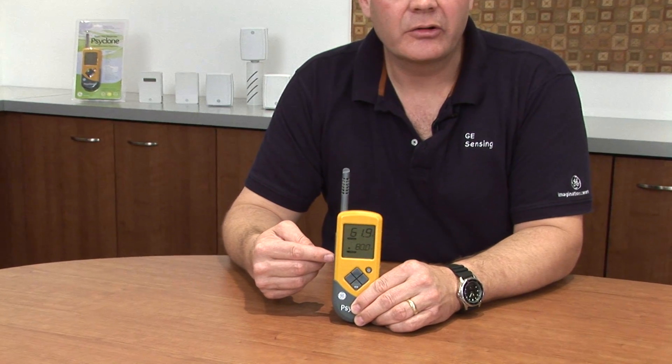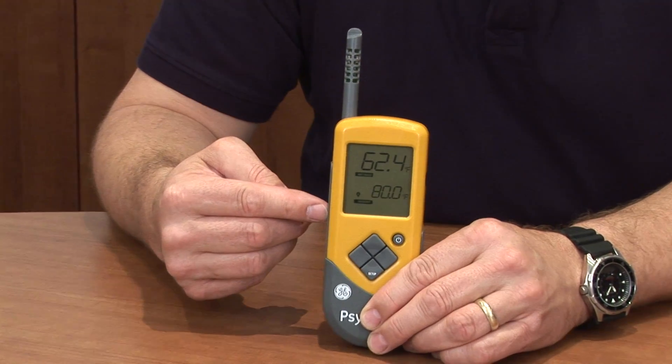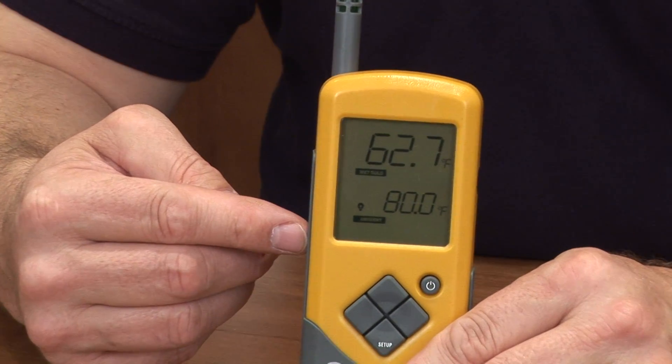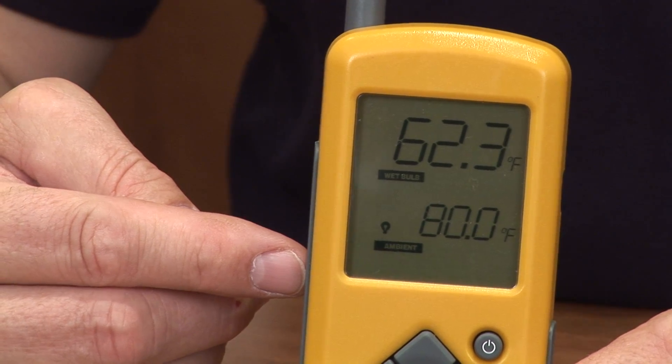The unit itself is robustly constructed with a rubberized hand grip and a belt clip for ease of carrying. The Protometer Cyclone has the ability to show various different psychrometric calculations — in this case, we're showing wet bulb. Being able to calculate this directly on the instrument means that you don't need to refer to psychrometric charts, where mistakes can often be made. The Cyclone has extremely fast response and will save you an immense amount of time when you're on the job site.